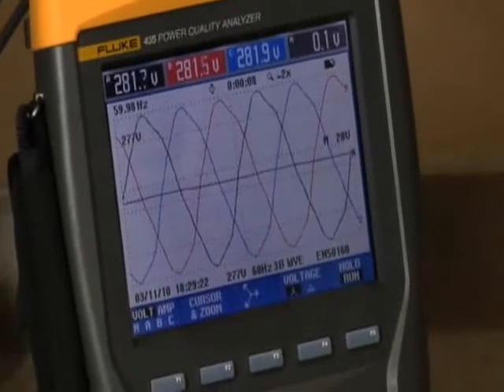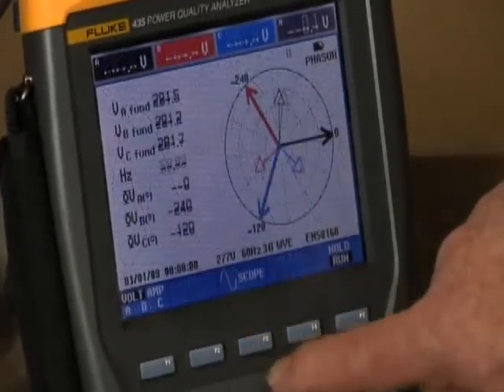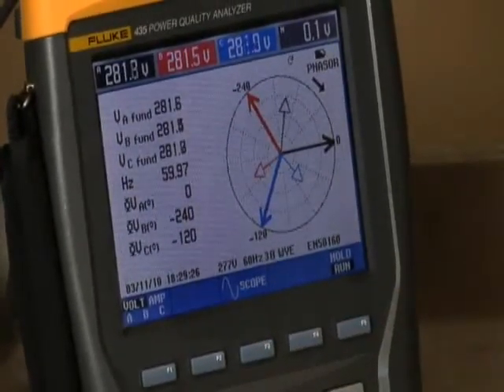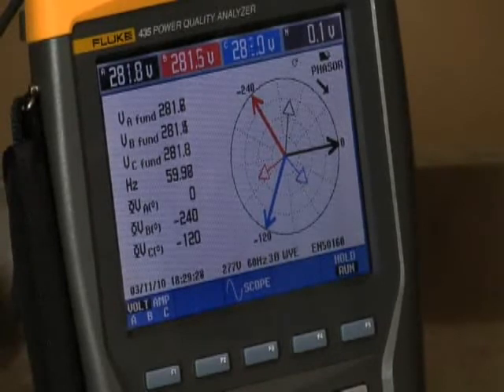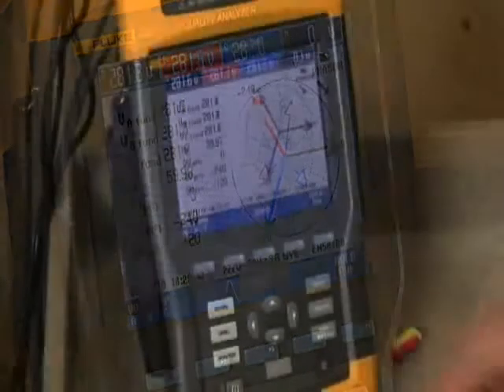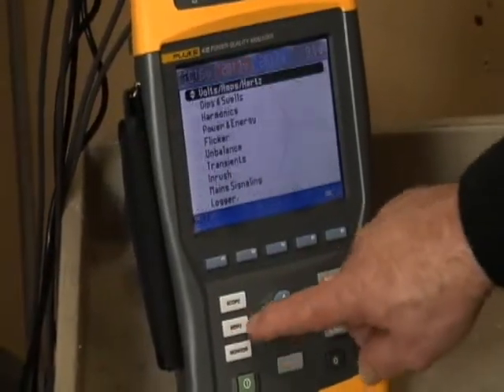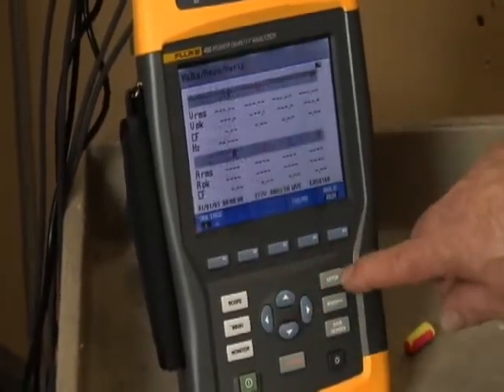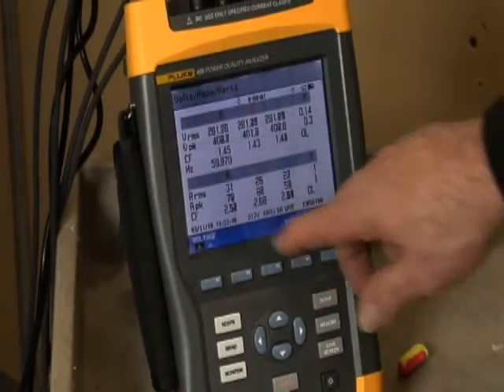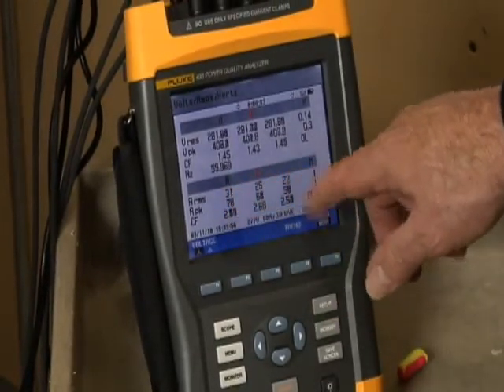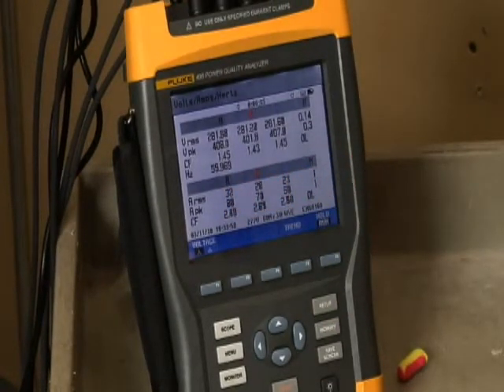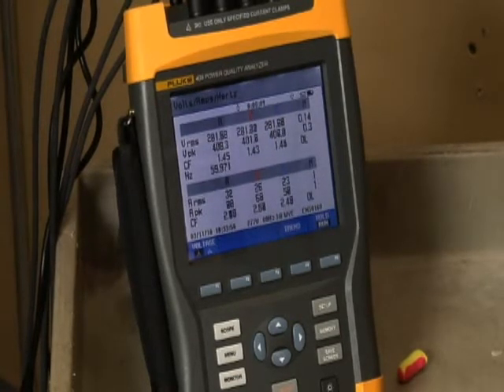Use the phasor screen to quickly check for unbalance. Since the length of the phasor represents voltage level, a shorter voltage phasor may indicate an unbalance problem. Compare the amps on each phase using the volts, amps, hertz screen. The maximum voltage unbalance is generally 2%. That is, the voltage on any one phase should not vary by more than 2% of the average of the 3 phases.